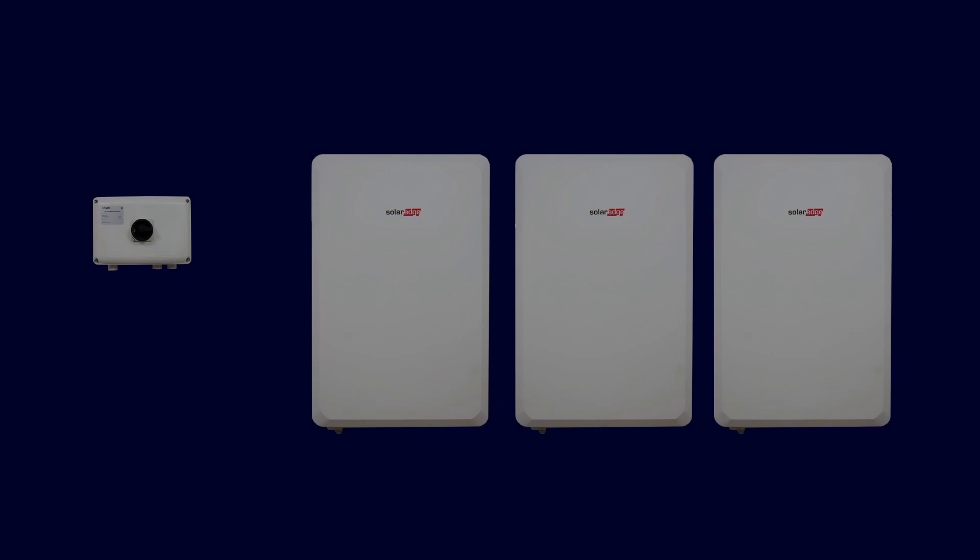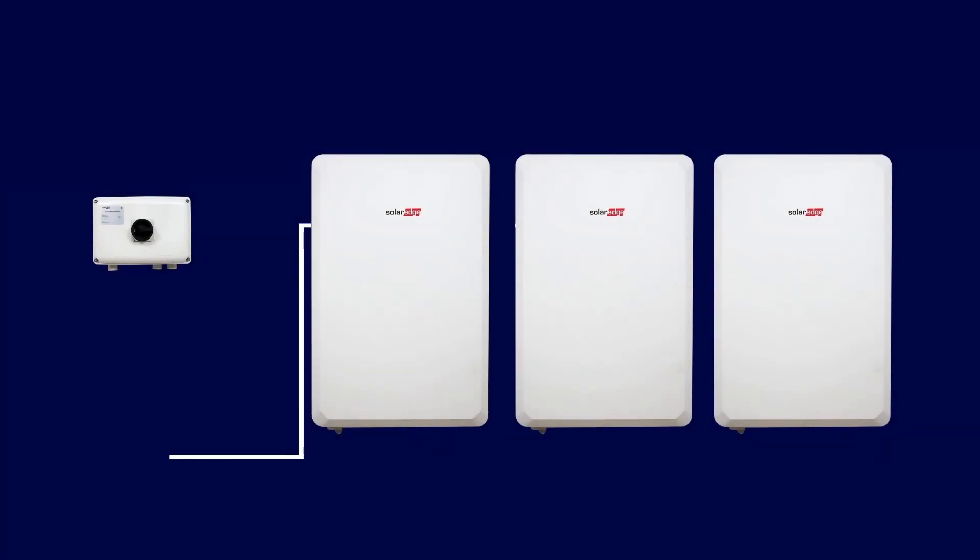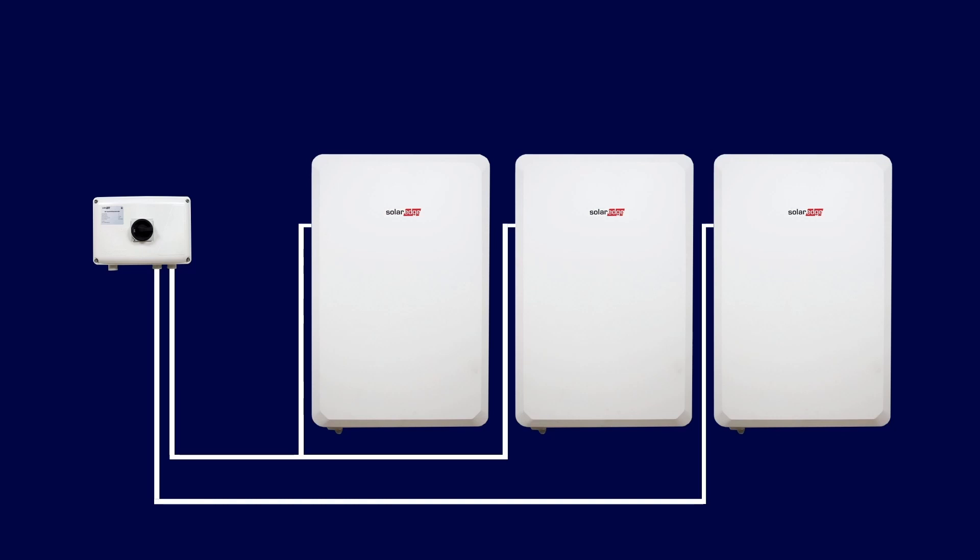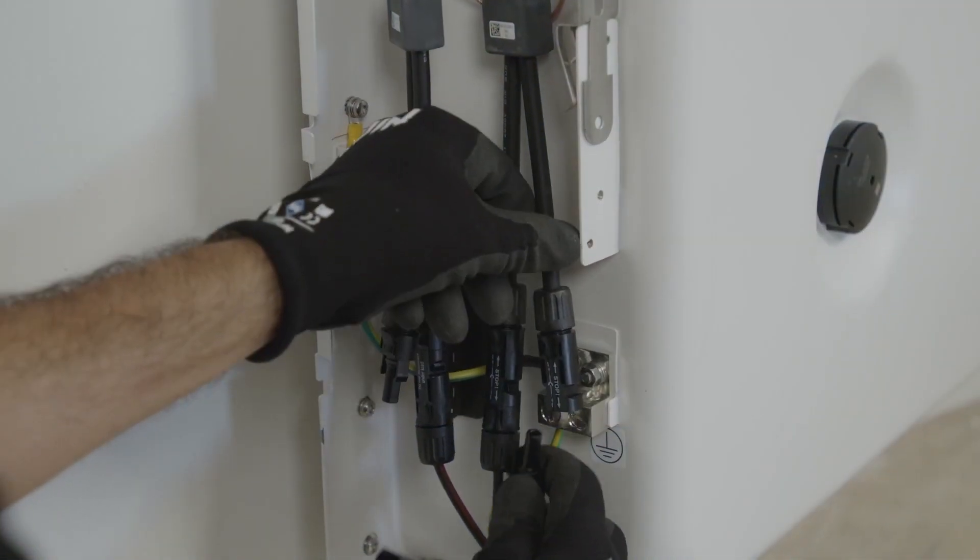If only two SolarEdge batteries have been connected, these can be wired directly to the inverter. If however three SolarEdge home batteries are being used, you'll need to use the DC combiner. So for that, two batteries need to be connected together using the Y branch connector and the third battery directly into the DC combiner.